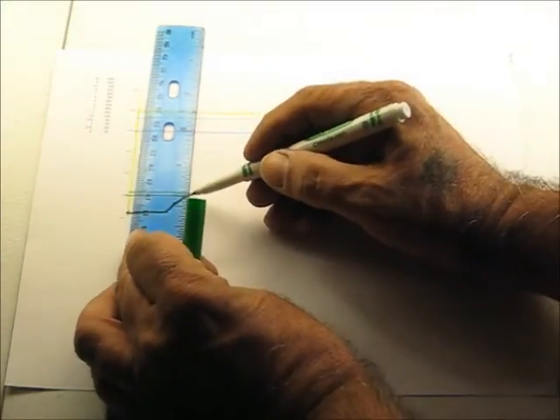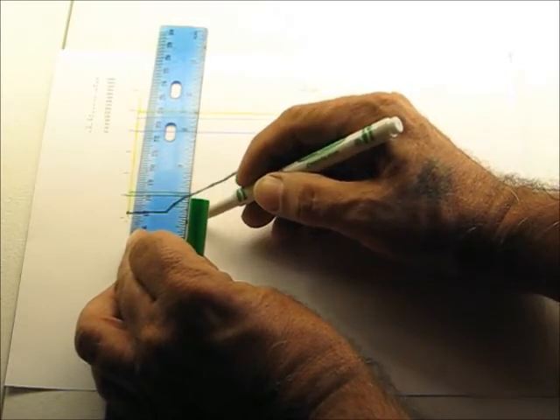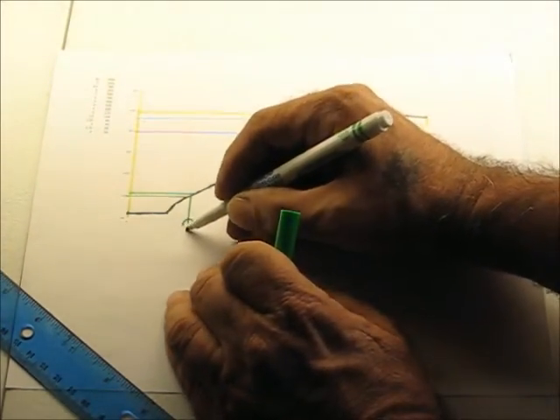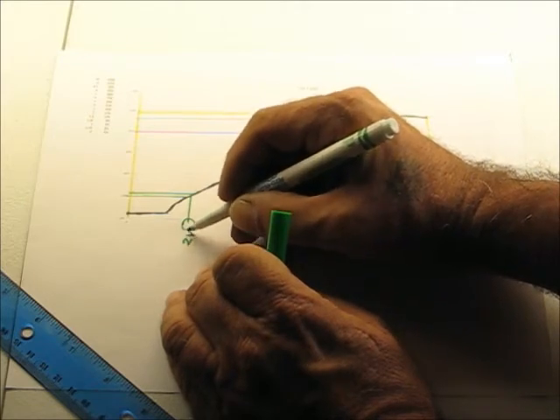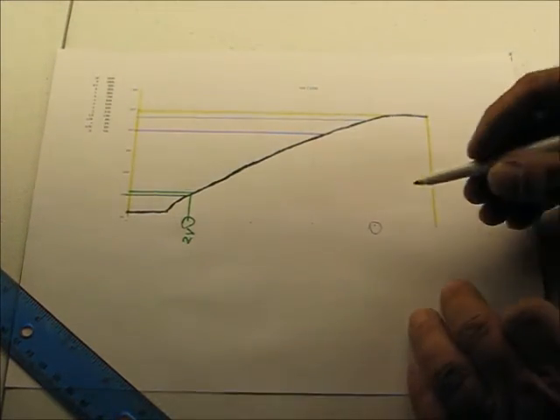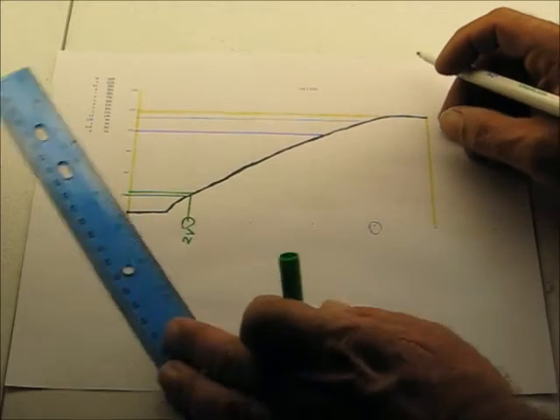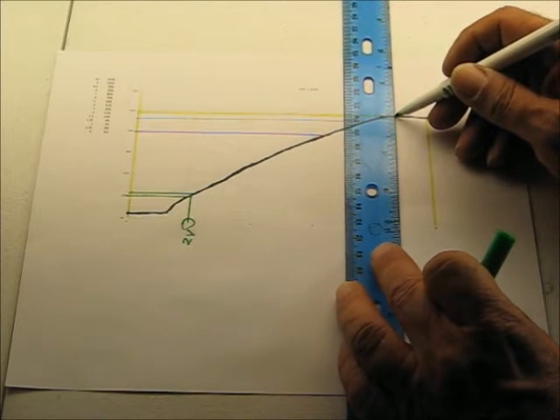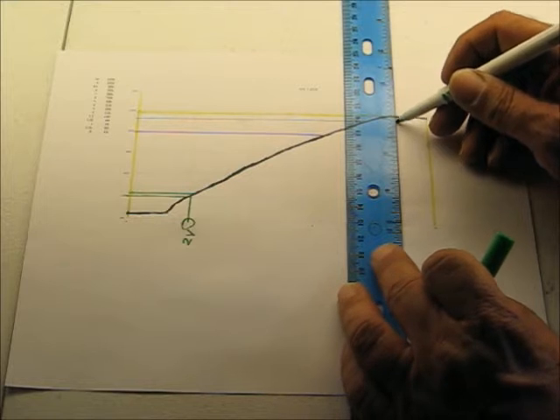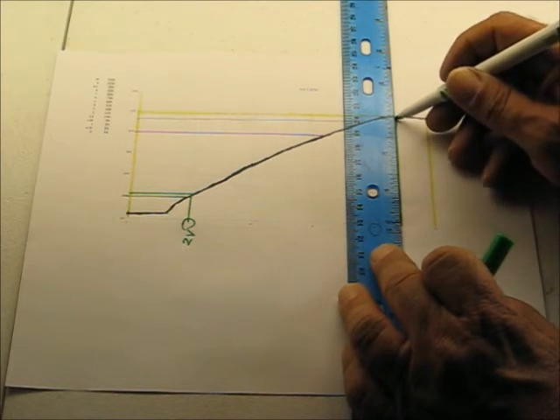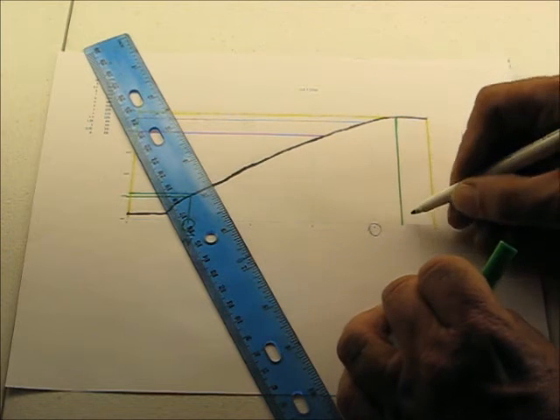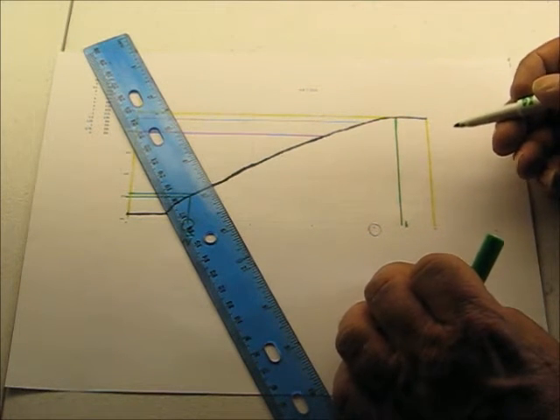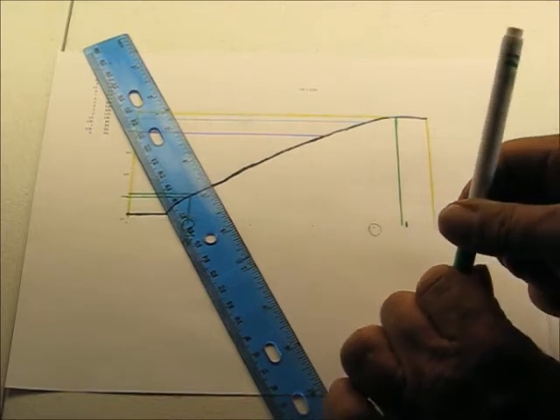On this controller, you would be looking for 2 volts or lower. This is 2 volts. And on your top end, you might want to go a little above the dimming curve for daylighting so that as daylight begins to come in, the lights don't respond immediately. So that's about 9 volts here. You're talking about 8.8 volts or something like that.